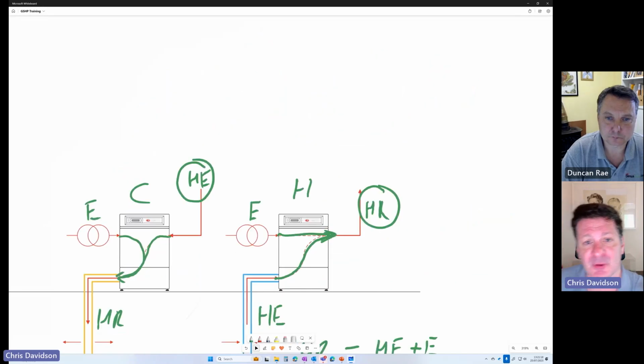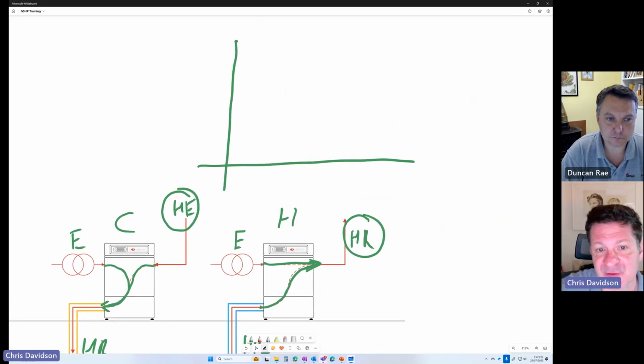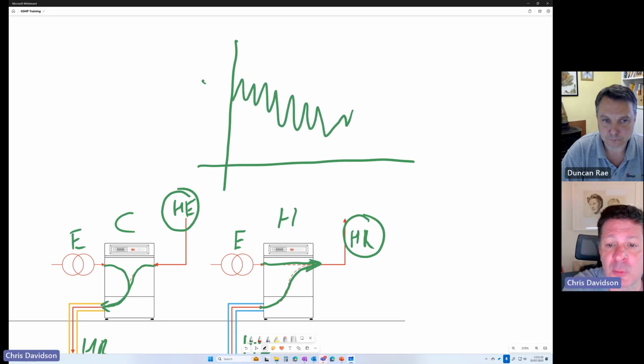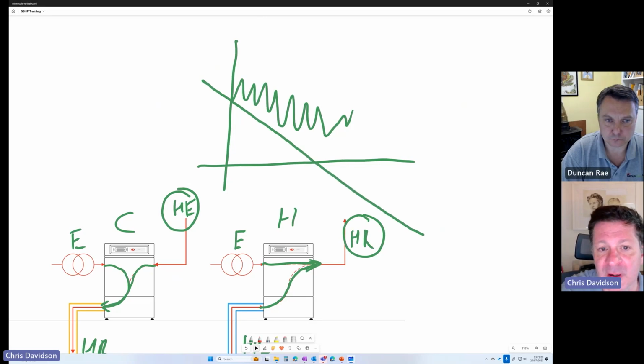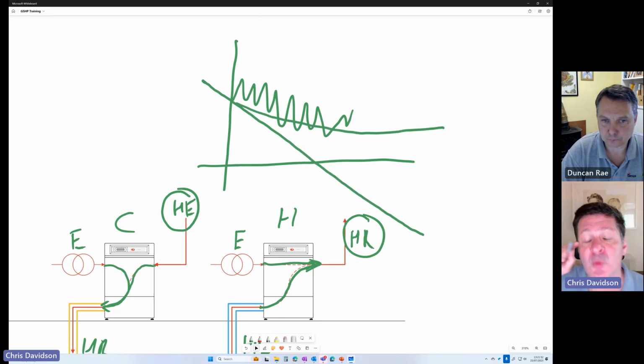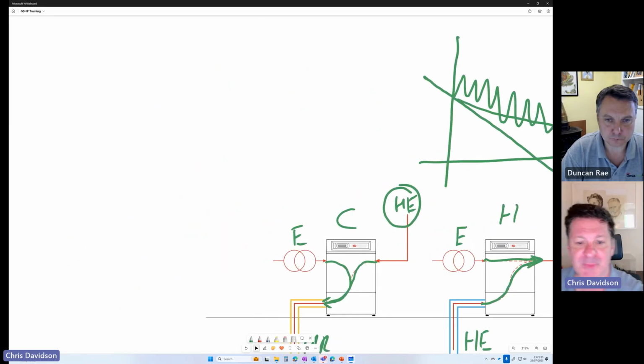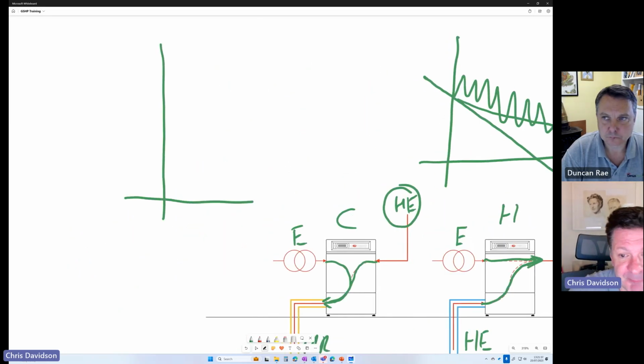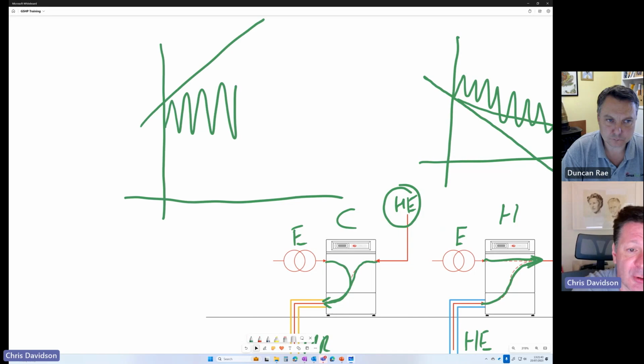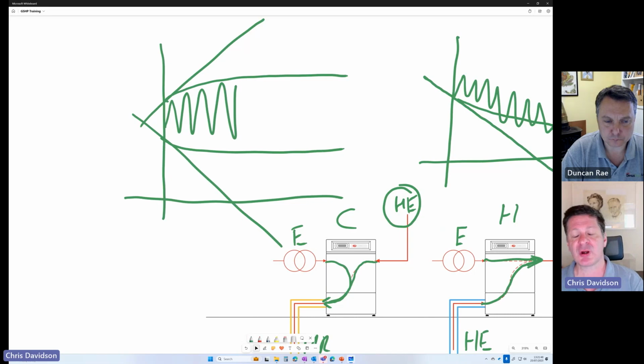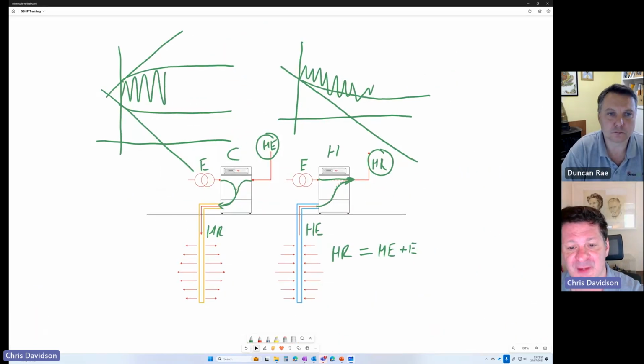And what I mean by sustainable in the long term: if we look at a heating only system for a start, then year on year we would expect that ground to get colder, but what we don't want is just getting colder and colder and colder. What we want it to do is tend to a limit within the efficient operation of the heat pump. If we're now looking at a heating and cooling system, then the graph will go in both directions. And again, we don't want it just getting hotter and hotter or colder and colder, but we want it to be working inside that efficient operation of the ground loop. So that's what we mean by a sustainable ground loop in the long term. The temperatures are manageable and within the capabilities of the heat pump.